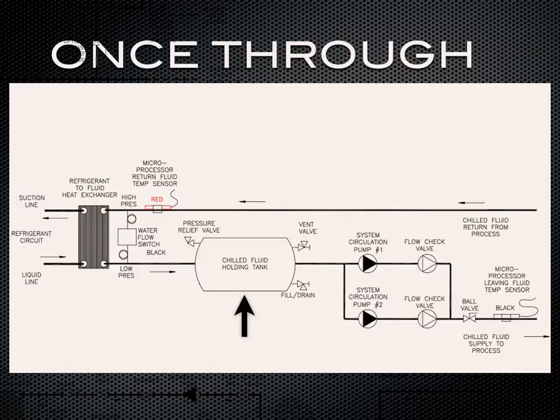So let's move along to the process water side here. You have your piece of equipment, and that's going to generate heat, and that heat's going to be transferred to the water or water glycol, and it's going to be brought back directly to that chiller evaporator, which is this piece right here. The heat's going to be rejected to the refrigerant side, and then it will reject it to a water source or out to the air. Then you're going to have your desired leaving water temperature going back to your tank, and then your pumps are going to pull off that tank and it will go out to your process.